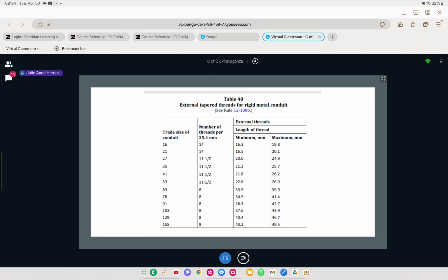You are 100% going to get a question based on this table: external tapered threads for rigid metal conduit. You'll absolutely get that, except where they'll try to trip you up is they won't give you the trade size. They'll say 3-inch rigid metal conduit, and you'll go, oh, Julia was awesome, she told me there was a table for this. You'll find the table and go, uh-oh, what's the trade size for 3-inch? What do we do?